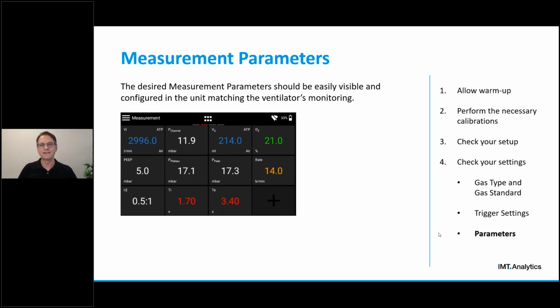So last but not least, on the settings side, we want to ensure that we look at the right measurement and have it set up in the correct unit of measurement, matching our device under test. So be aware that ventilator and test equipment manufacturers sometimes use different terms for exactly the same thing. For example, one ventilator may use a term called P-peak for the maximum pressure during the inspiration phase, while another device would probably call it PIP, which stands for peak inspiratory pressure. Or one ventilator could use the term rate for the breath rate, while another device might use the term frequency.